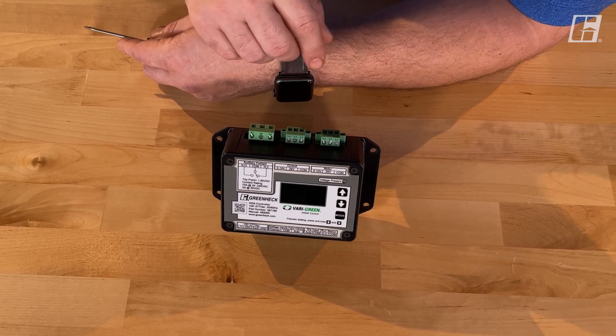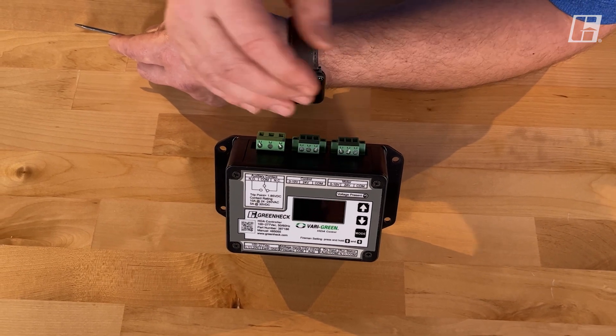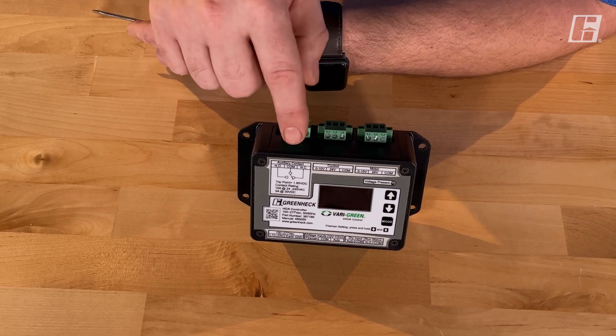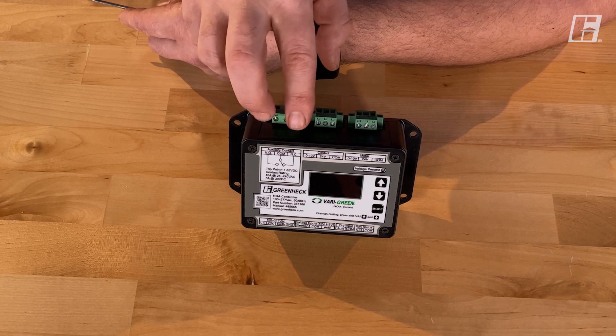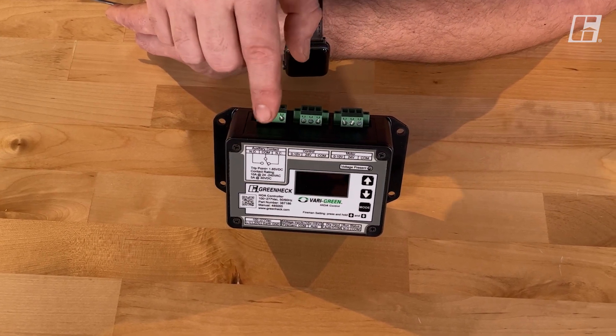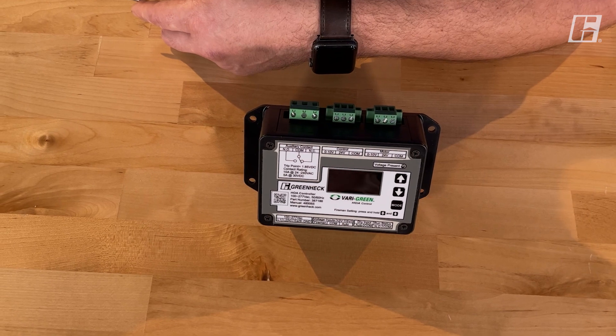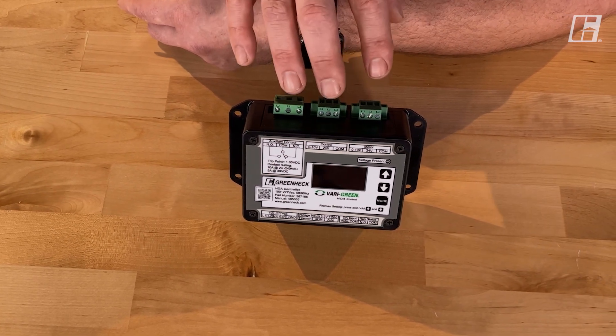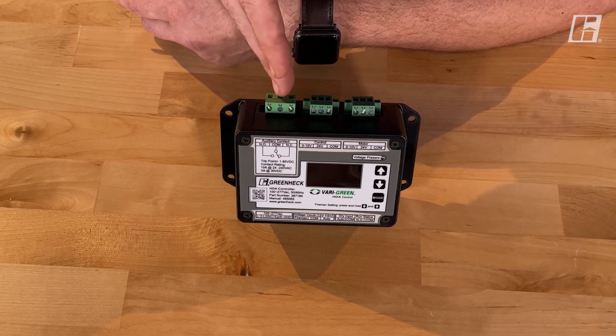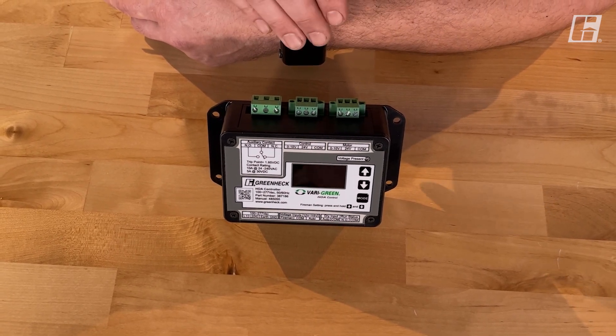One more terminal across the top: the auxiliary contact. Anytime this control sees a run command — a two-volt or better signal — this will change states. There's a common in the middle with a normally open and a normally closed terminal. This is most traditionally used to bring power in and pass it to a damper actuator when the motor is running. So you tell the fan to run, this changes state, power is passed to the damper actuator, it opens, and then the soft start of the Vari-Green motor brings the fan up to speed.